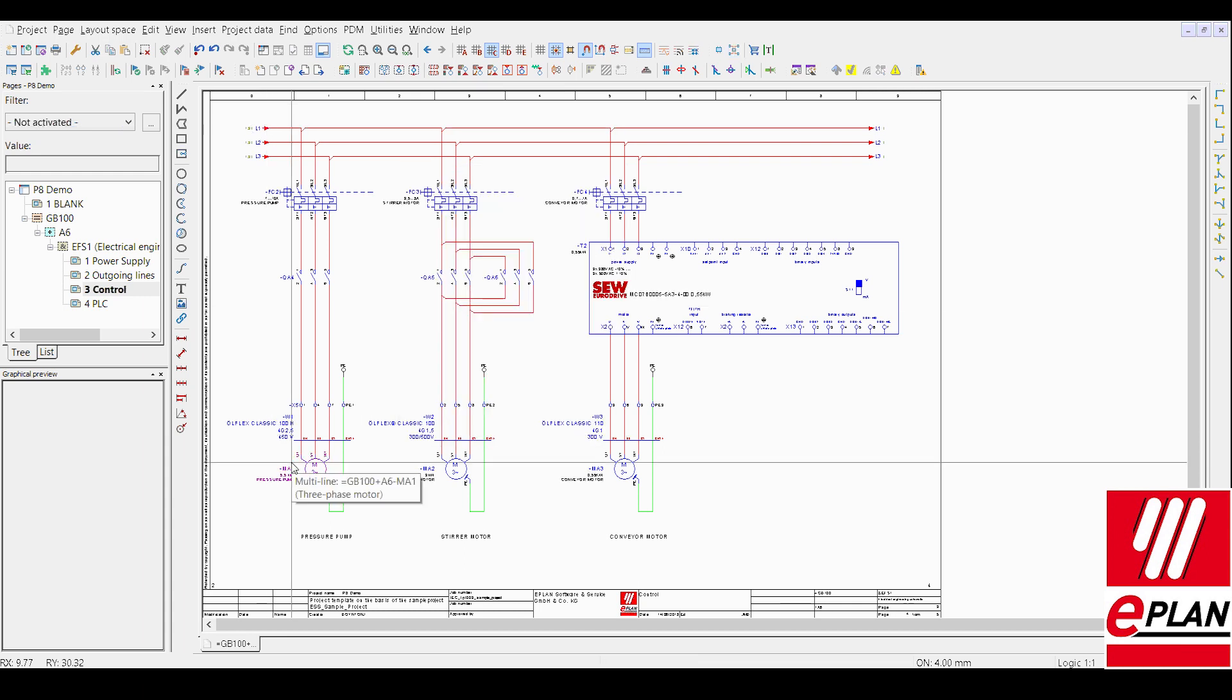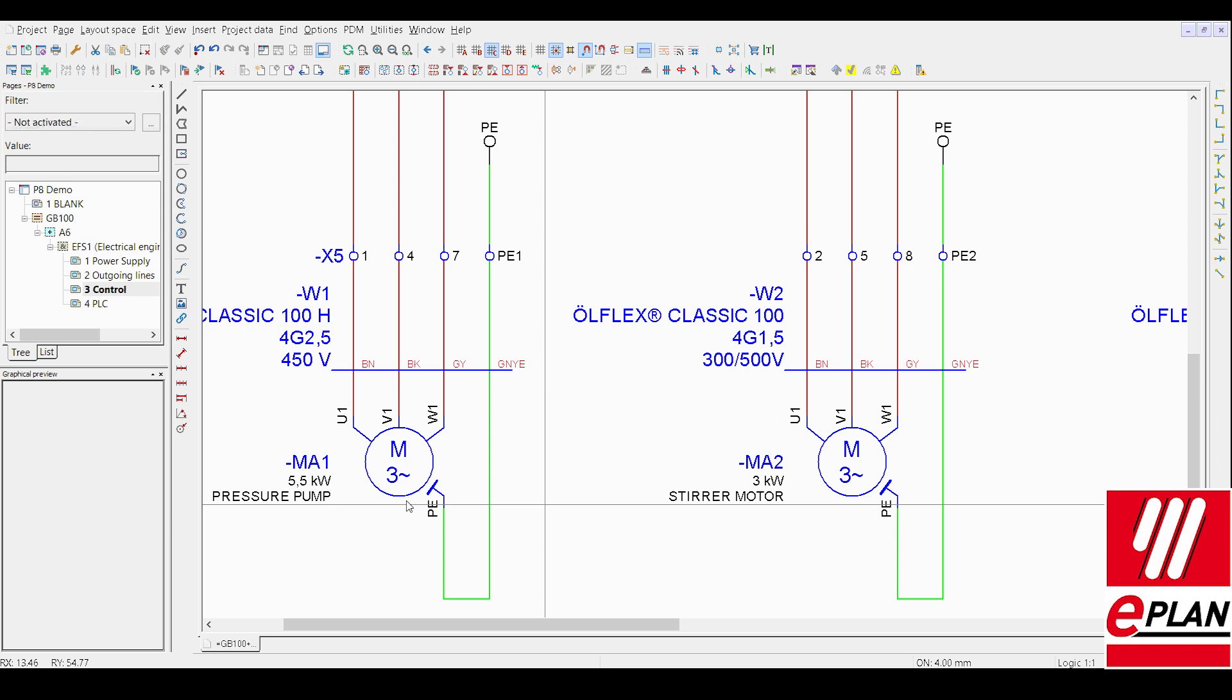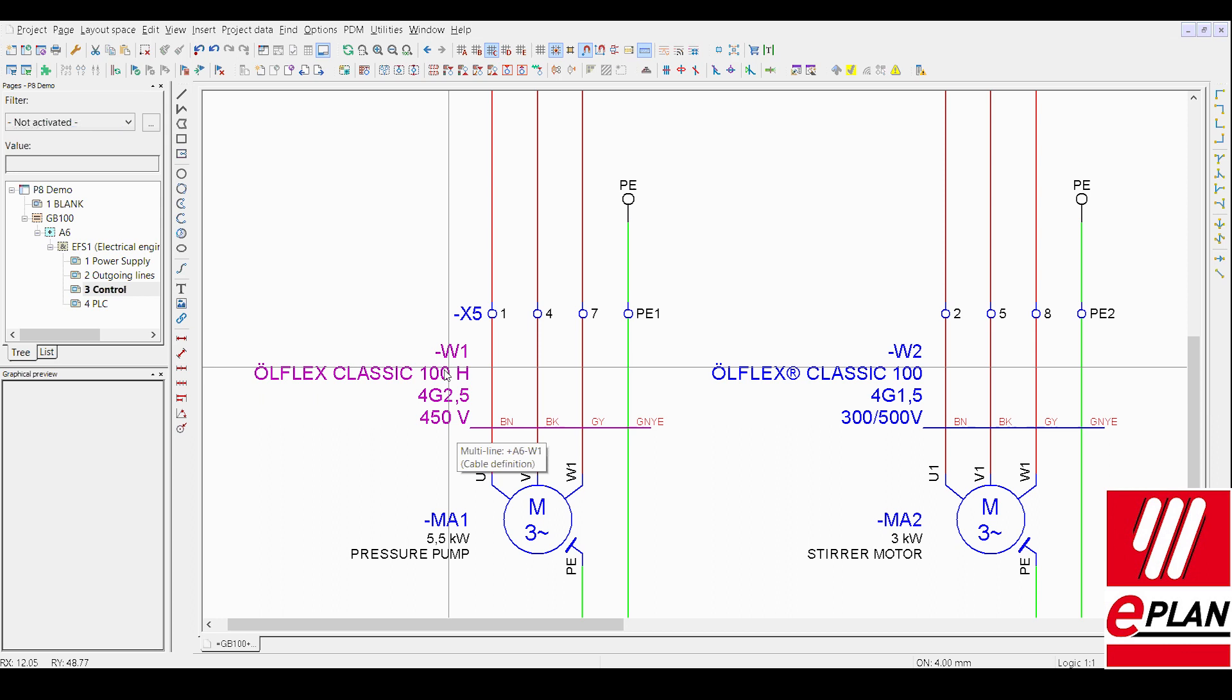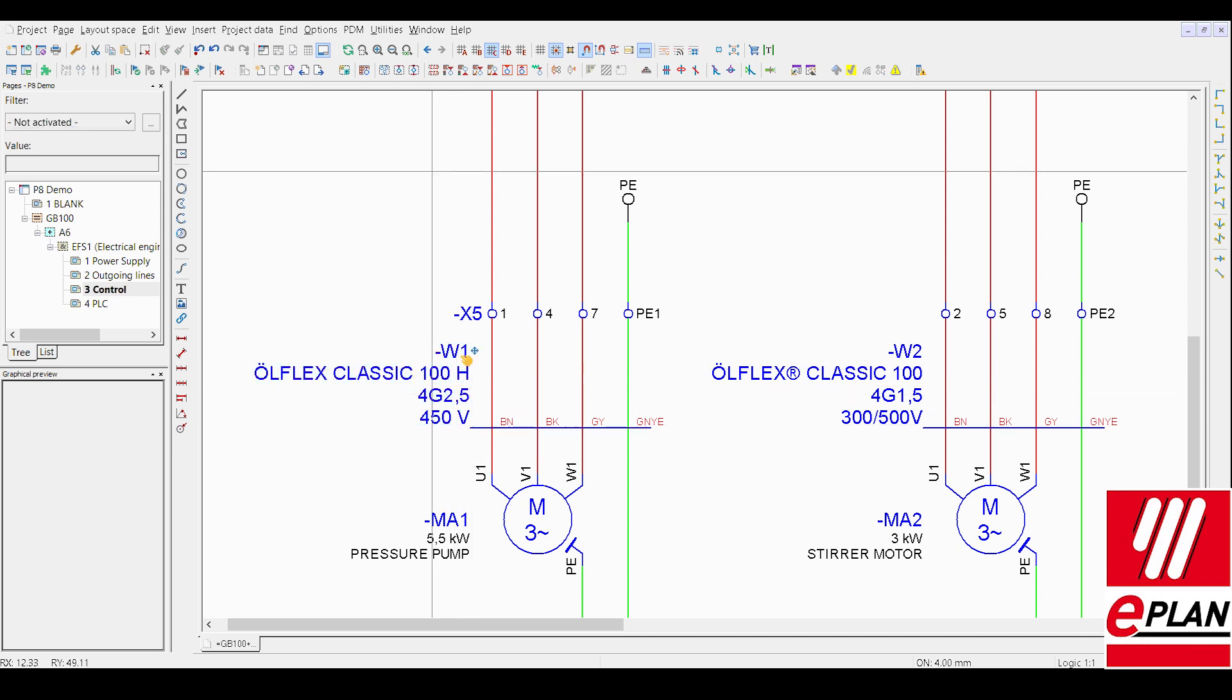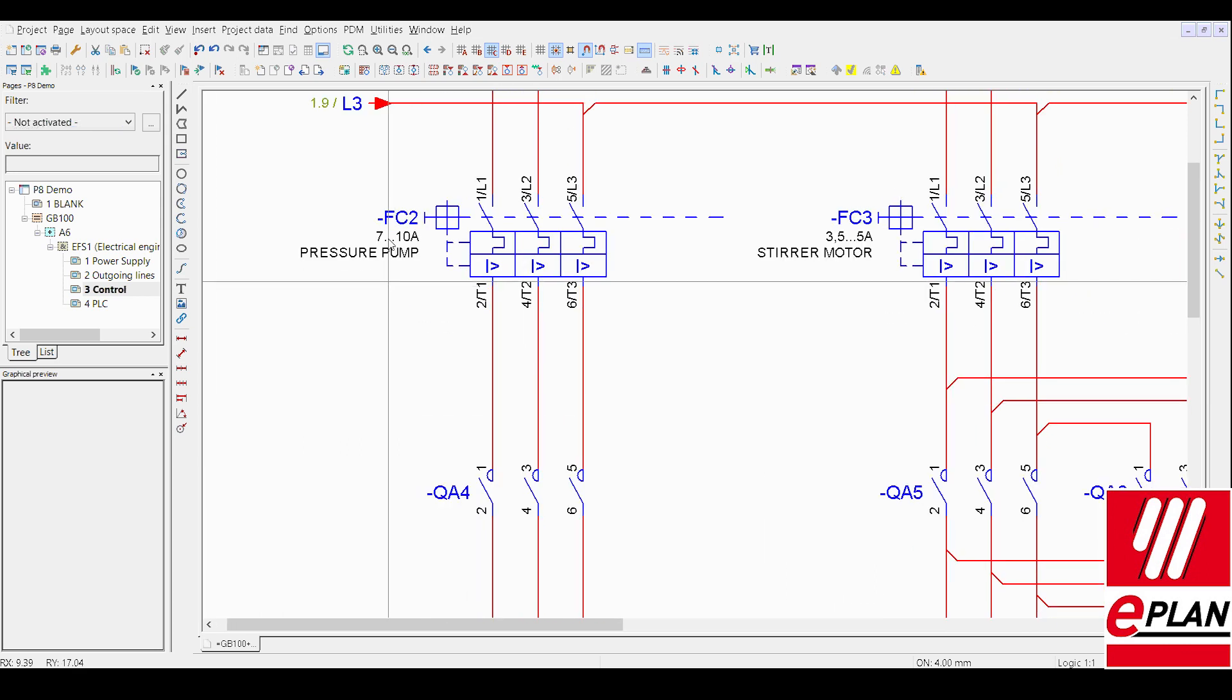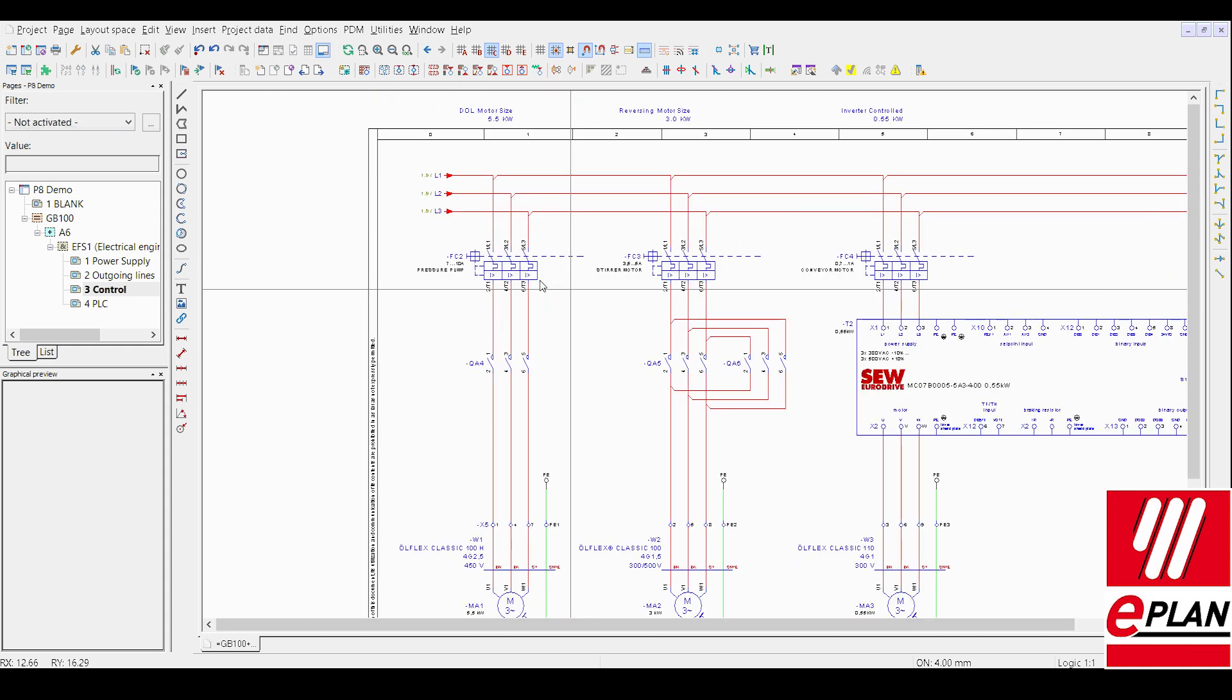As we can see down on the drive here we've got the ratings come through and the part numbers will also reflect that. The cable here we can see a 2.5mm cross section and on this particular arrangement a 7 to 10 amp protection item.